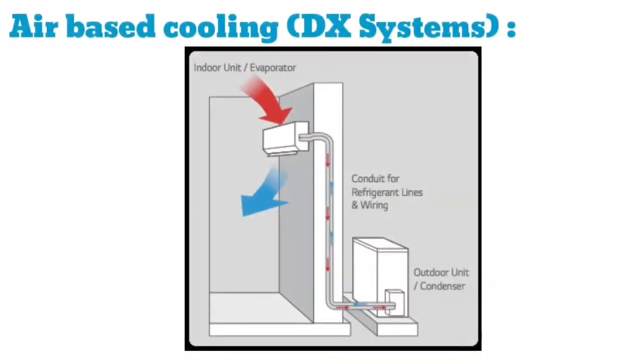DX stands for direct expansion and is a term that uses refrigerant as the cooling medium. With DX cooling, refrigerant flows through the cooling tubes and air is blown over the tubes covered with fins. The air does not come in contact with the refrigerant, but only with the cold metal surface of the coil. Since the air is cooled directly by the refrigerant, the cooling efficiency is higher.